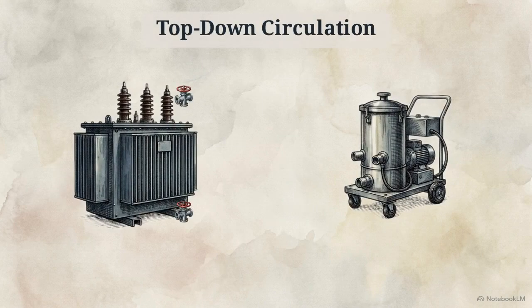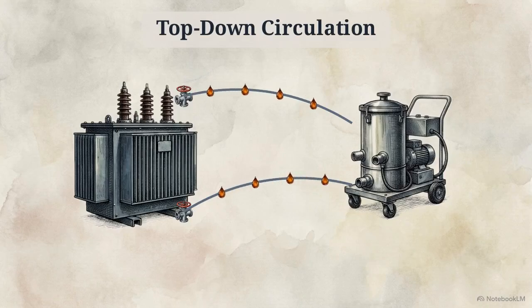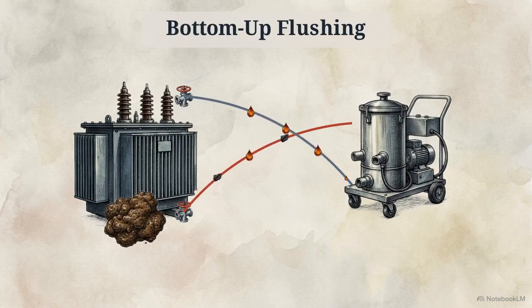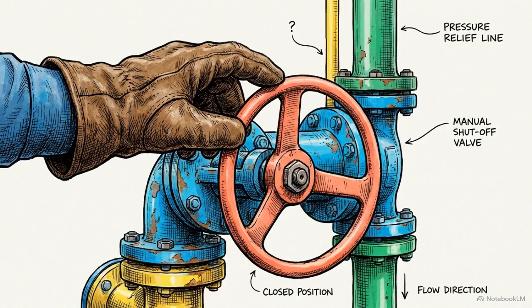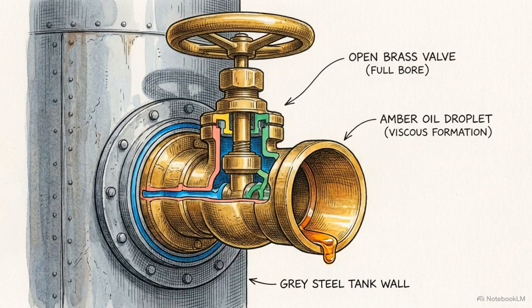For fresh units, connect the filter's inlet to the top valve and outlet to the bottom to create a top-down circulation loop. For older, sludged units, reverse this connection for the first 24 hours to flush contaminants from the bottom. Close the radiator valves to retain the heat you are about to apply, but ensure at least one valve remains open to allow for thermal expansion.